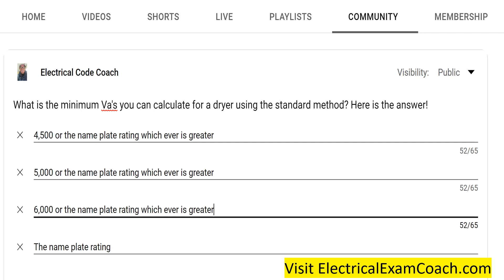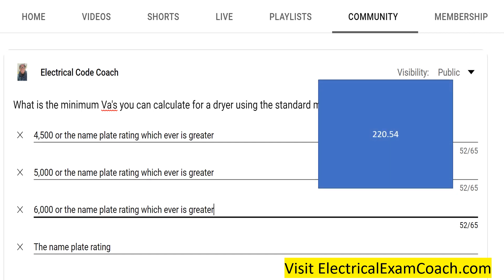Today's question is: what is the minimum VA's you can calculate for a dryer using the standard method? That may sound like an odd term if you're not familiar with Article 220, but there are two different methods for calculating load calculations — the standard method and the optional method — both prescribed in Article 220. This one is asking how you deal with dryers for household electric dryers demand factors.